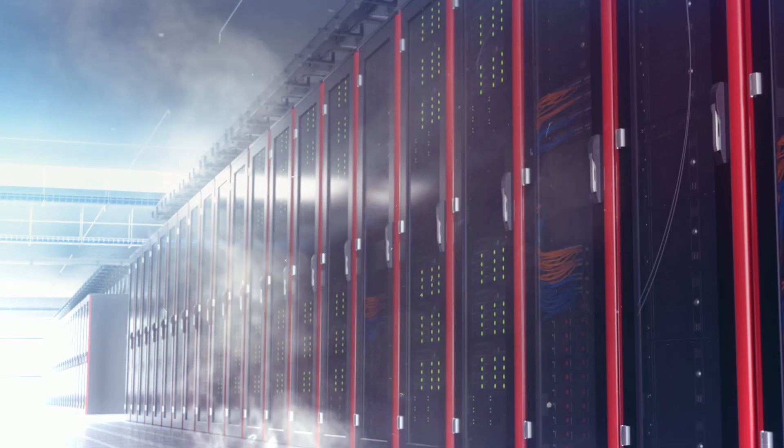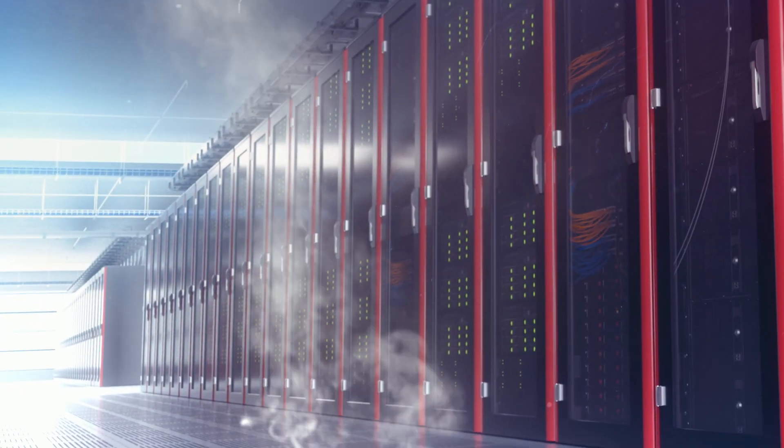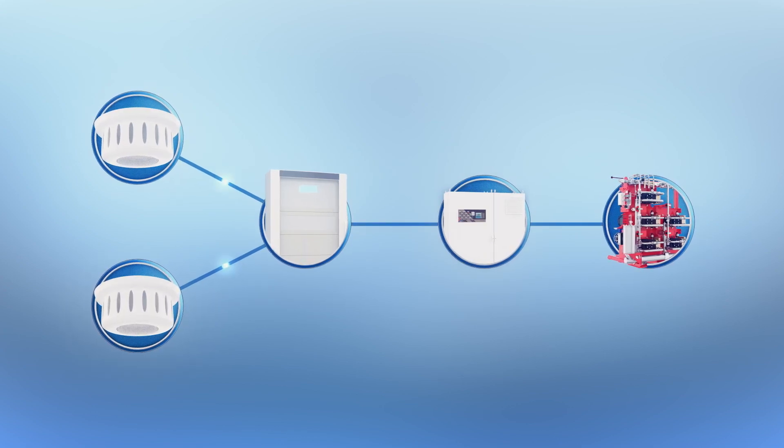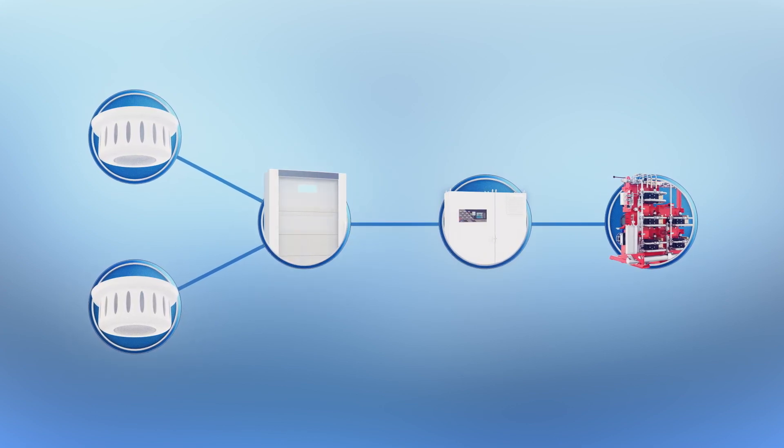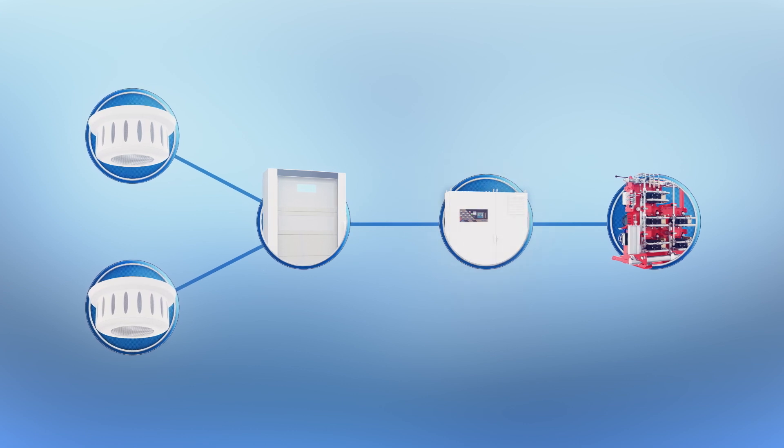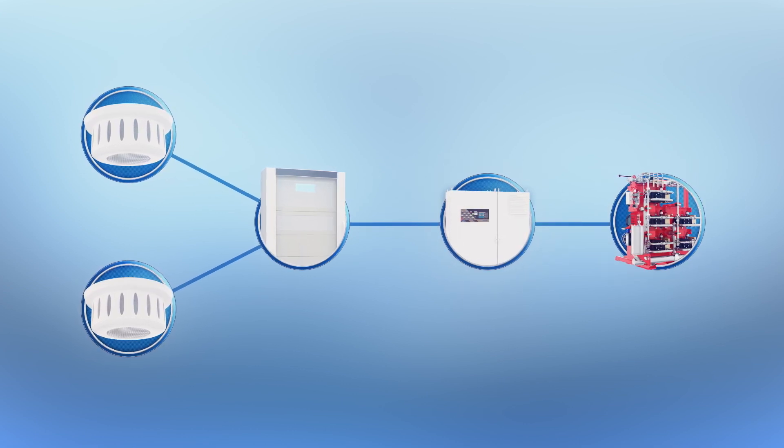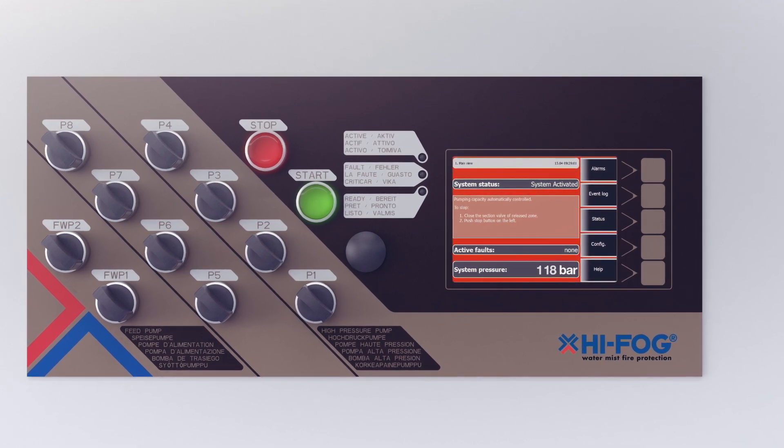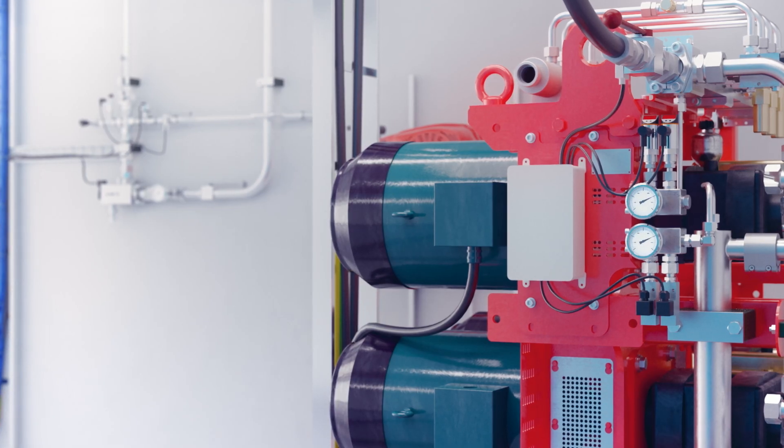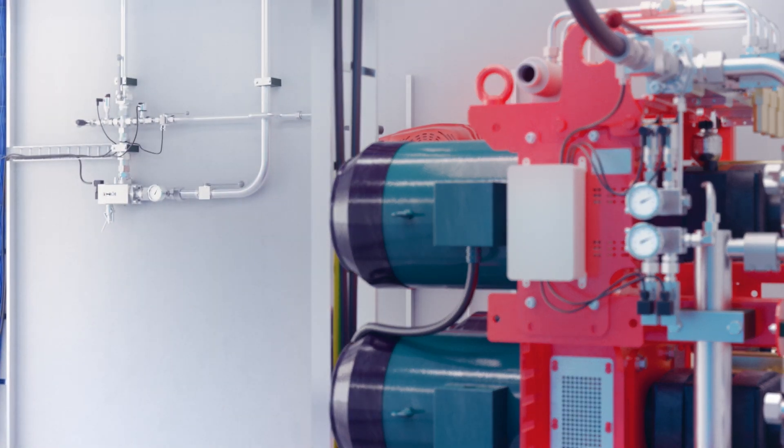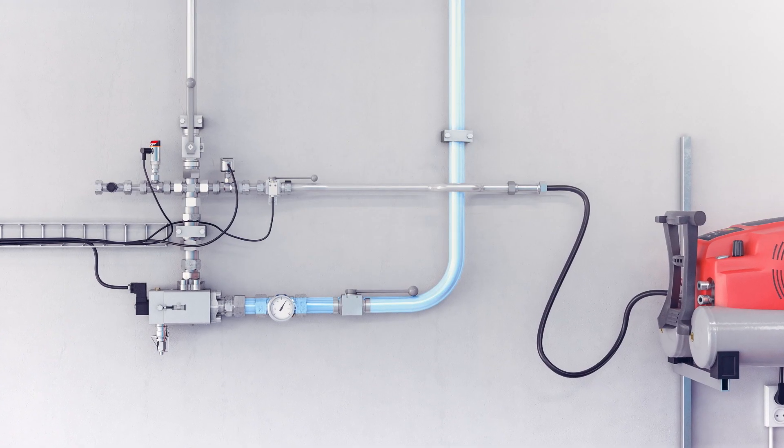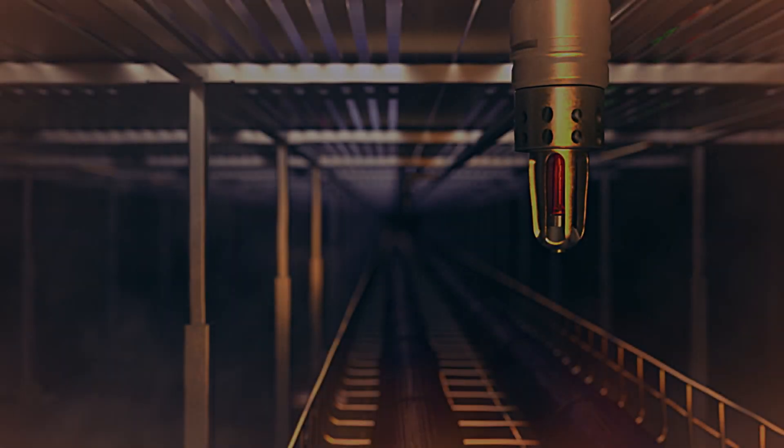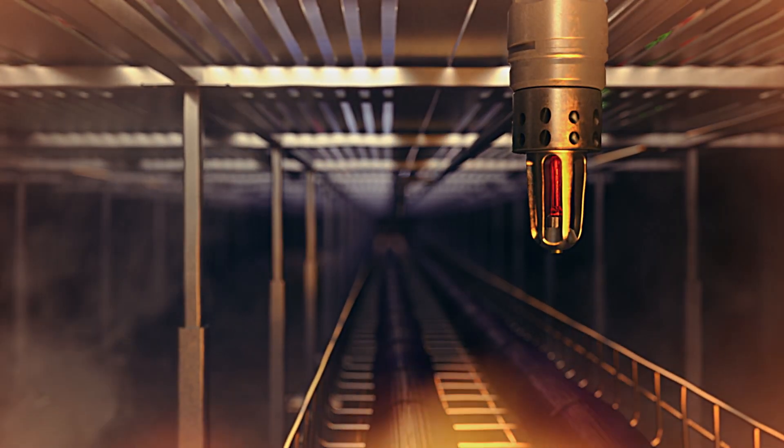The data hall is typically equipped with early sensing smoke detectors. The system activates when one or several detectors send a signal to the release panel. The release panel responds by sending a signal to the control cabinet, which immediately starts the HIFOG pumps, which then will generate high pressure. A signal is also sent to open up the valve. Water mist is only released to the area where it is needed to fight fire.